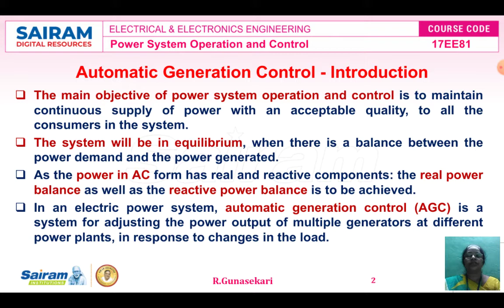Suppose the power grid requires that generation and the load closely balance moment to moment. The frequent adjustment to the output of the generators is necessary. The balance can be judged by measuring the system frequency. Balance means real power balance, reactive power balance. If the system frequency is increasing, more power is generated than the used power, which causes all the machines in the power system to accelerate.